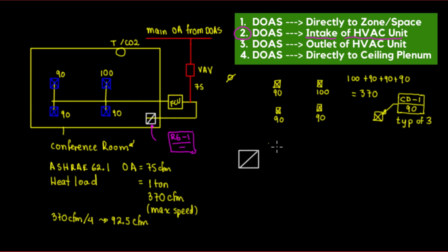Yeah, okay. So is this going to be 370 CFM? See, it's return air? Maybe. Is it going to be 370 CFM? Not really. So what happens is actually the following. Again, I'm going to go to pink in here. Now that we're injecting directly this 75 CFM to the back of the FCU, and this FCU can only give you 370 CFM, right?